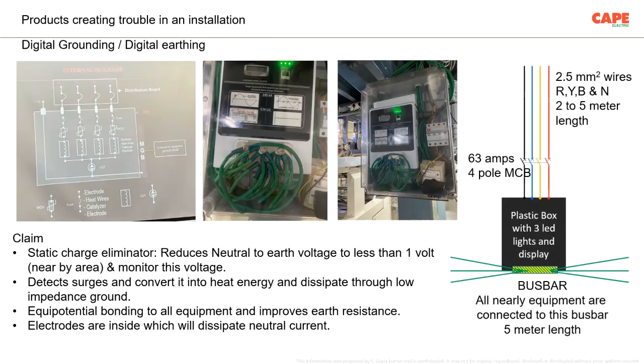What they do is, there is a plastic box, three small wires of 2.5 square mm go into the plastic box, and there is a 63 amp MCB. I am showing you one of the case studies which I made. There is a plastic box with 3 LED lights, a lot of MOVs are connected according to the manufacturer, and there is a bus bar, a large bus bar. You can see here, there is a large bus bar. All the outgoing equipment, nearby equipment, the protective earthings are connected to this common bus bar. Then the claim is that this is the device which is going to solve all your problems.